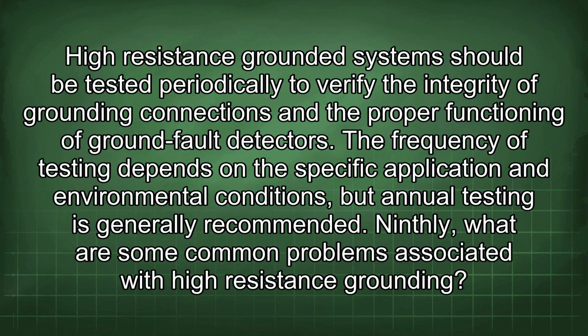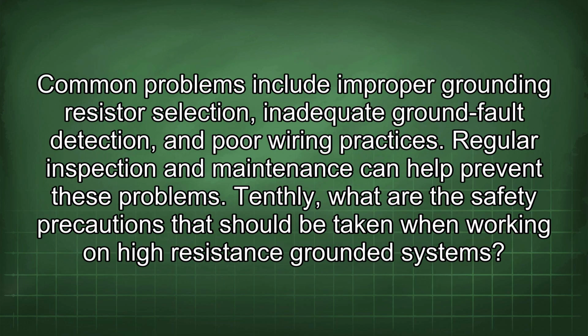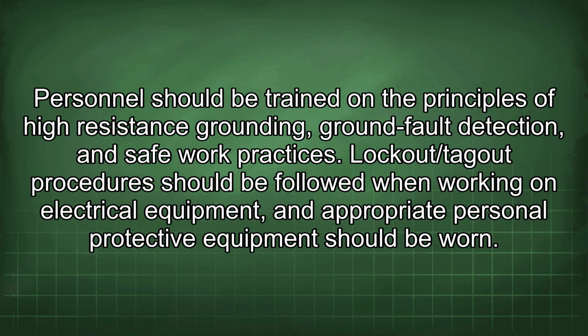Ninthly, what are some common problems associated with high resistance grounding? Common problems include improper grounding resistor selection, inadequate ground fault detection, and poor wiring practices. Regular inspection and maintenance can help prevent these problems. Tenthly, what are the safety precautions that should be taken when working on high resistance grounded systems? Personnel should be trained on the principles of high resistance grounding, ground fault detection, and safe work practices. Lockout/tagout procedures should be followed when working on electrical equipment, and appropriate personal protective equipment should be worn.